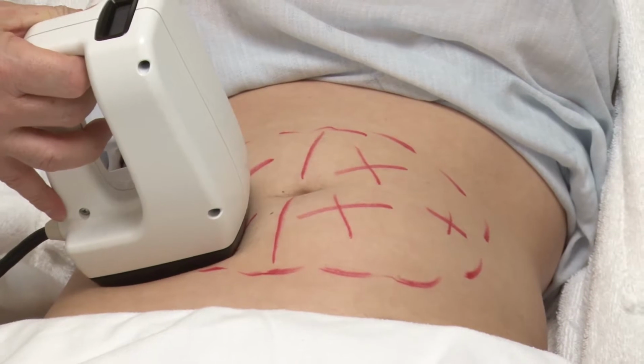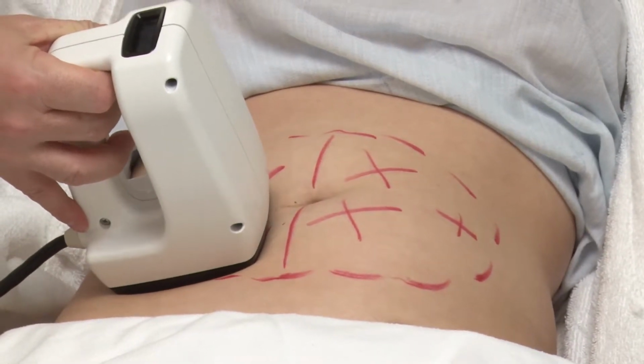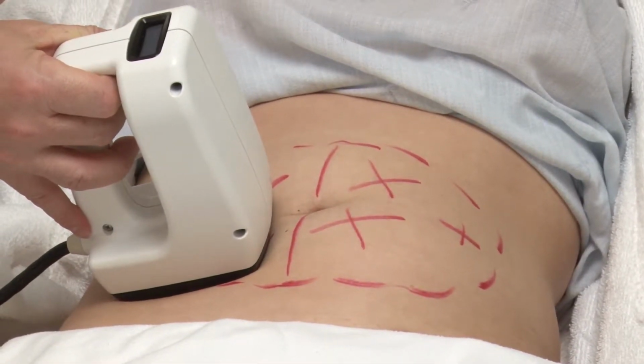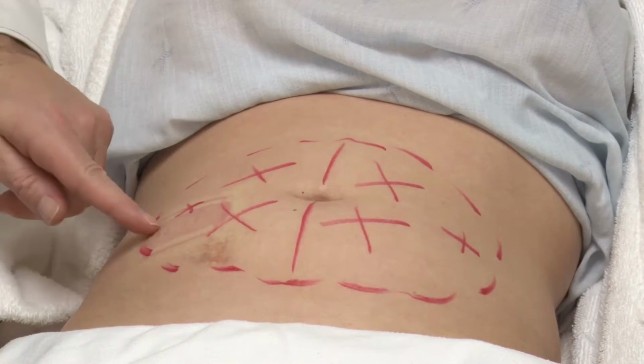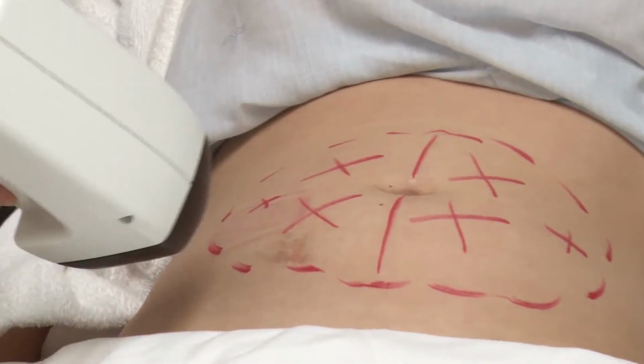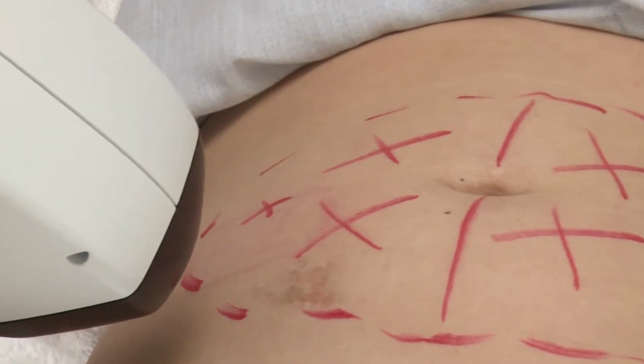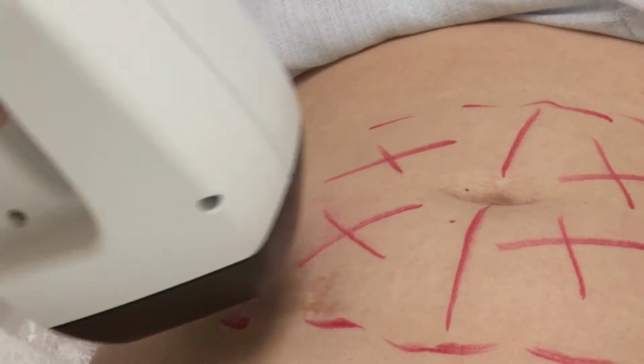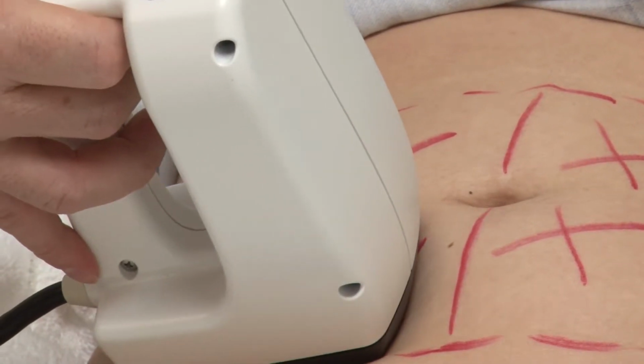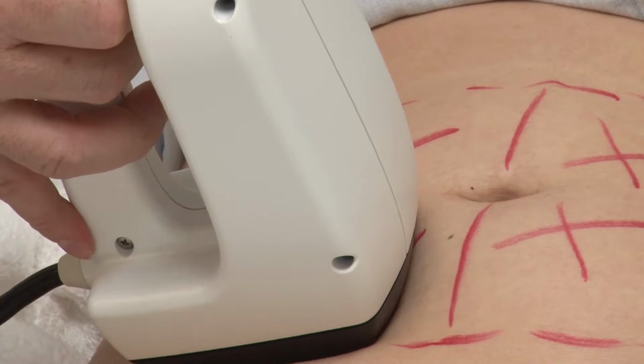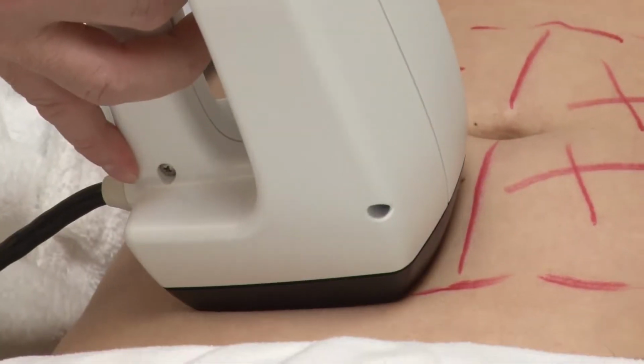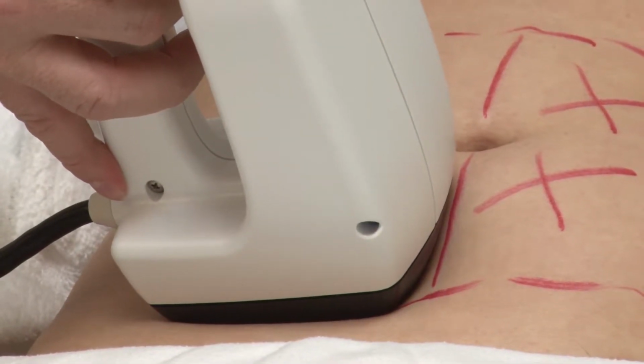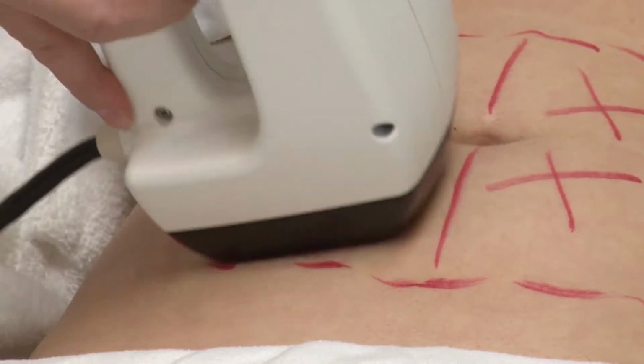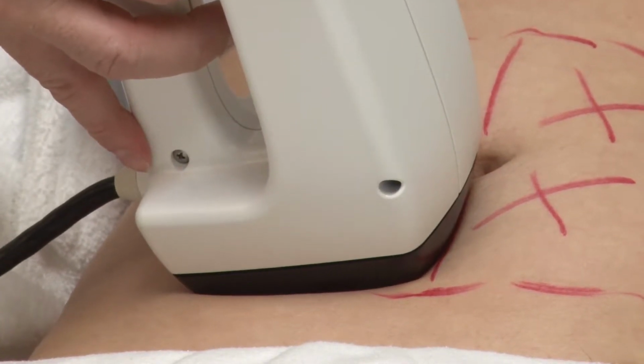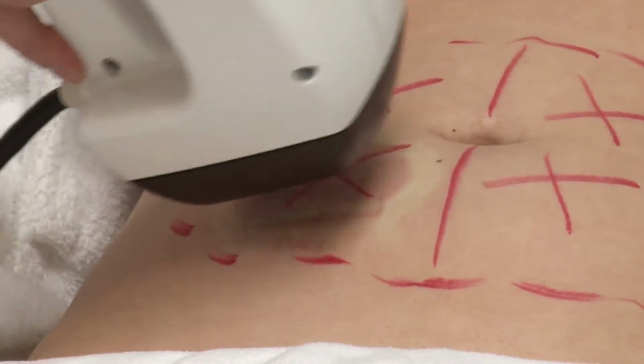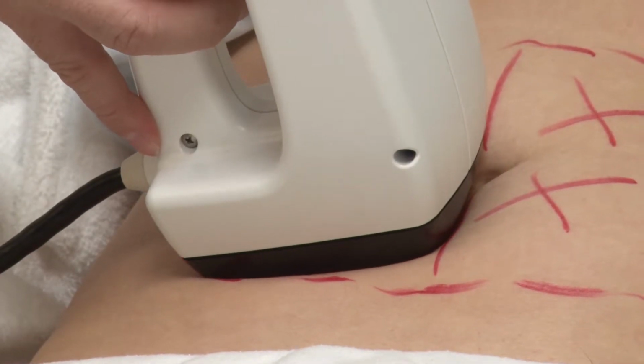So we put our device on the skin, press the button, you hear the suction, and you can feel that suction. The patient has a little erythema from the suction. We overlap 50%, just like fractional resurfacing, 50%. And we're going to heat for 2 seconds, and we overlap 50%. Let the patient get used to suction. We're already up to 33 degrees, so there's a little bit of warming, a little bit of suction. Ask the patient, is that reasonably comfortable? So comfortable with the suction.